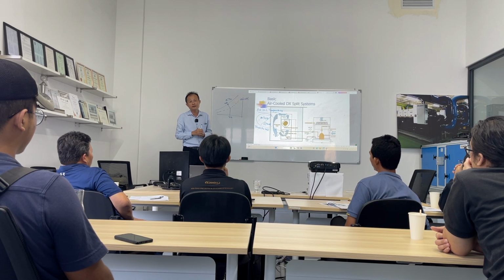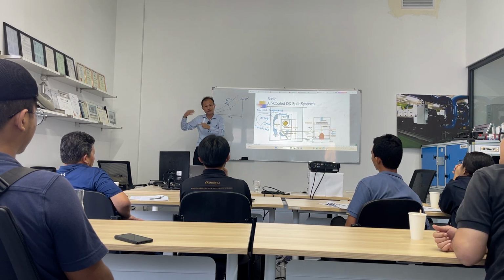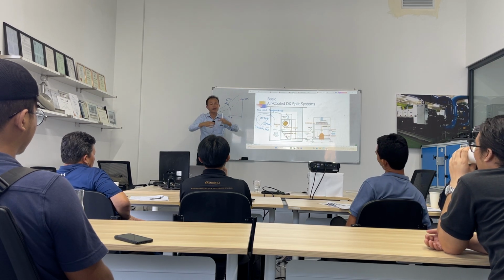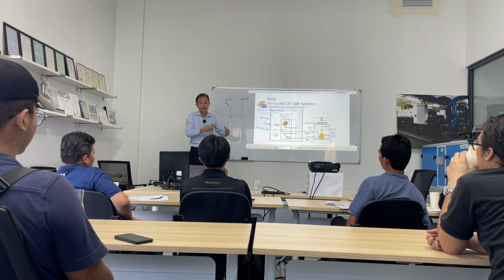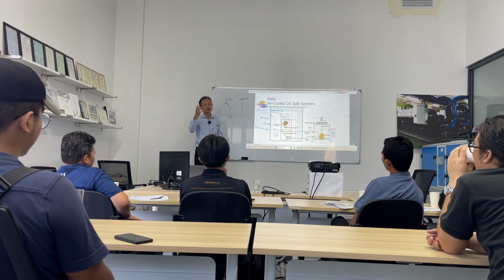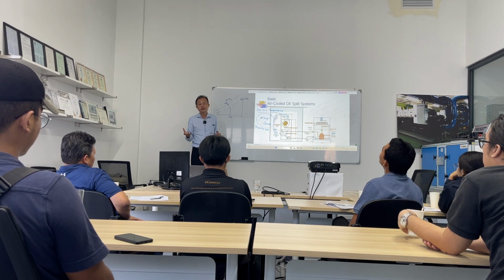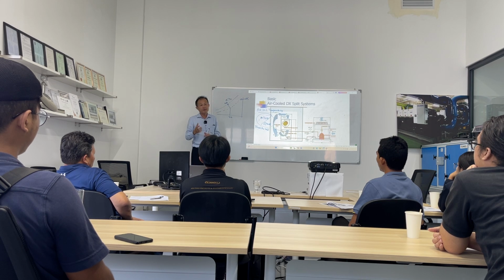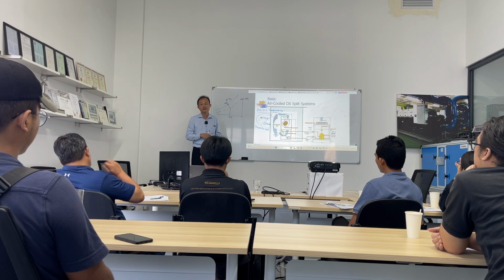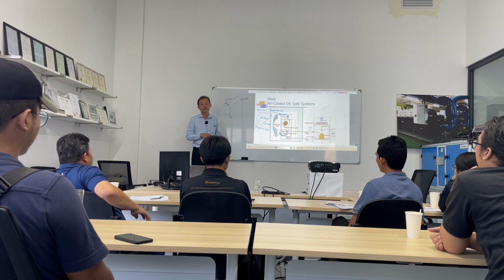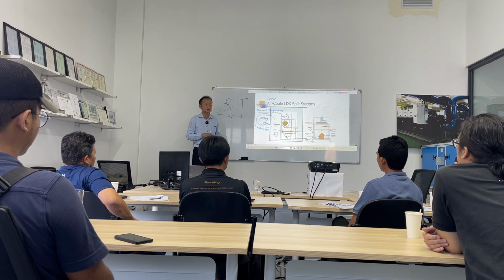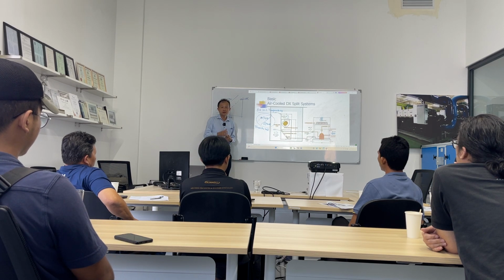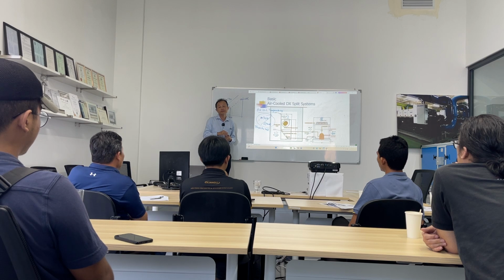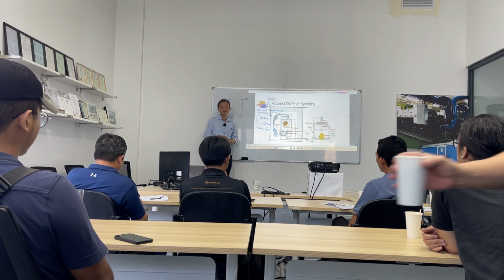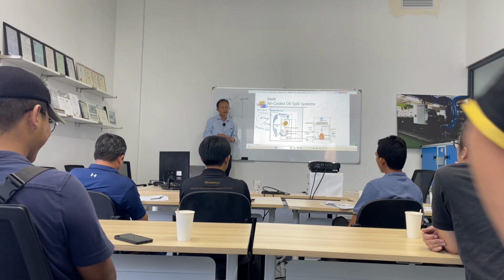A lot of consultants don't design the heat load properly in the way that I have just presented. If all the components come in, and then how many CFM, then use the mixture formula and calculate what the on-coil temperature is. They just use BTU and give you the total, they don't give you the on-coil temperature. So if they don't give you the on-coil temperature, there are many ways for the supplier to give you under-specified capacity. And this is very important for us to take note of when we handle a project. Almost 15%, very big capacity, very dangerous.